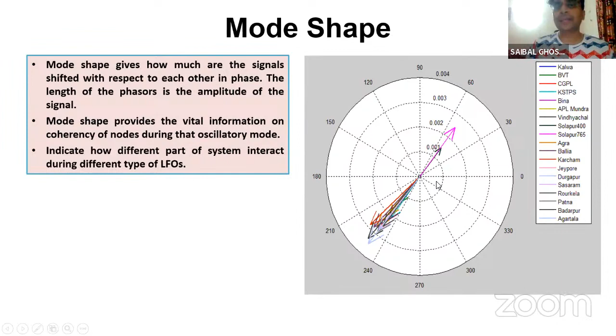So based on this mode shape, you can decide which are your coherent groups in the system participating in the oscillation. Here we can see that this is Solapur and this is Vindhyachal - these are in one direction and the rest are in the other direction, forming two different groups. Some generators may be in the perpendicular, meaning they are not participating in this oscillation. So when these two groups are clearly identified, you can know the boundary across which the system is oscillating.